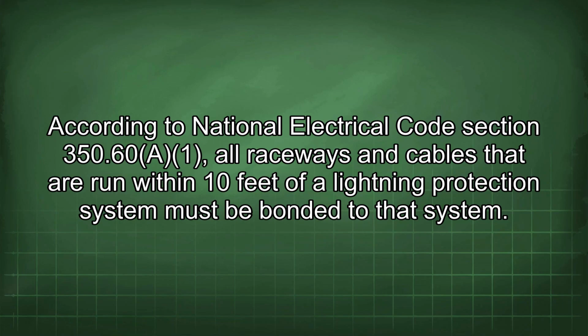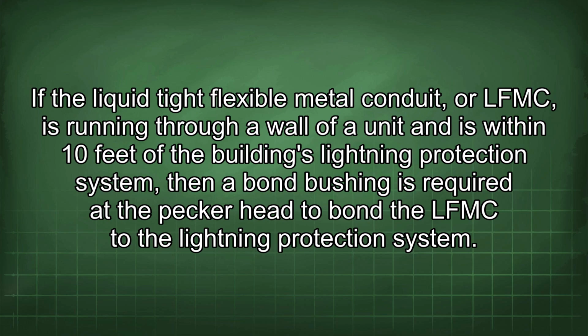According to National Electrical Code Section 350.60, all raceways and cables that are run within 10 feet of a lightning protection system must be bonded to that system. If the liquid-tight flexible metal conduit, or LFMC, is running through a wall of a unit and is within 10 feet of the building's lightning protection system, then a bond bushing is required at the pecker head to bond the LFMC to the lightning protection system.